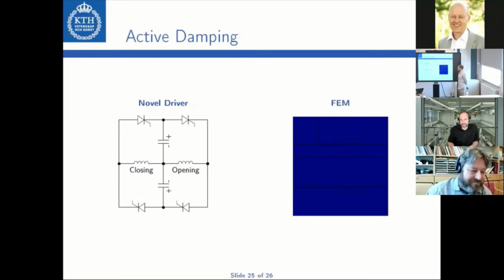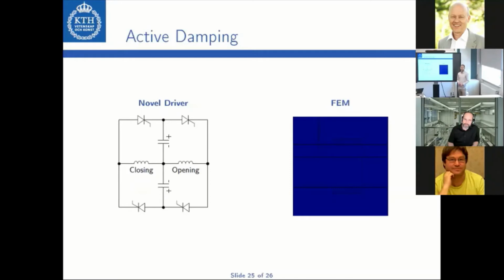Yes, I think it would be good. The advantage of this one is that it has two capacitors less than the conventional configuration. And as I also mentioned in publication 4, from a practical point of view, the drive circuit of the Thomson coil actuator is also a limitation for practical reasons, because you need to recharge the capacitors after the operation. If you want to carry out auto reclosing, you can calculate what kind of voltage you have available in the substation to recharge the capacitors. Is it possible in 300 milliseconds, let's say, and is it possible for two capacitors in this time?